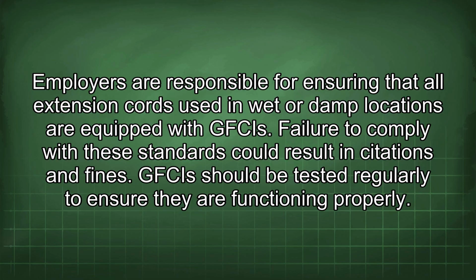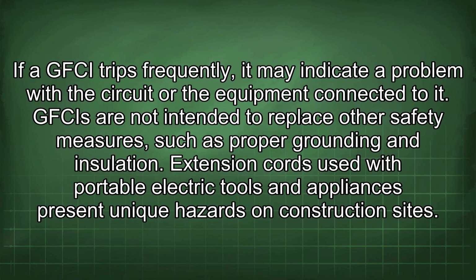Employers are responsible for ensuring that all extension cords used in wet or damp locations are equipped with GFCIs. Failure to comply with these standards could result in citations and fines. GFCIs should be tested regularly to ensure they are functioning properly. If a GFCI trips frequently, it may indicate a problem with the circuit or the equipment connected to it. GFCIs are not intended to replace other safety measures such as proper grounding and insulation.